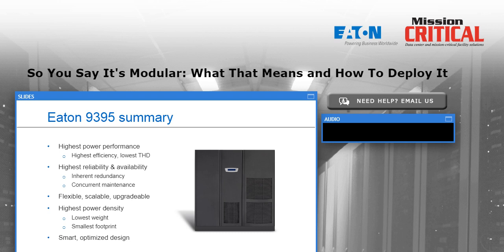However, if you have a UPS system that's 8 or 10 years old and you're operating at very light load levels, take a look at your efficiency on that machine and see if it's time for an upgrade, based on the amount of years of operating at possibly inefficient levels. High reliability and availability, just like in the smaller versions. If I put on one more UPM module or power module in a system like this than I actually need to support the critical load, then I already have N+1 redundancy for that application.